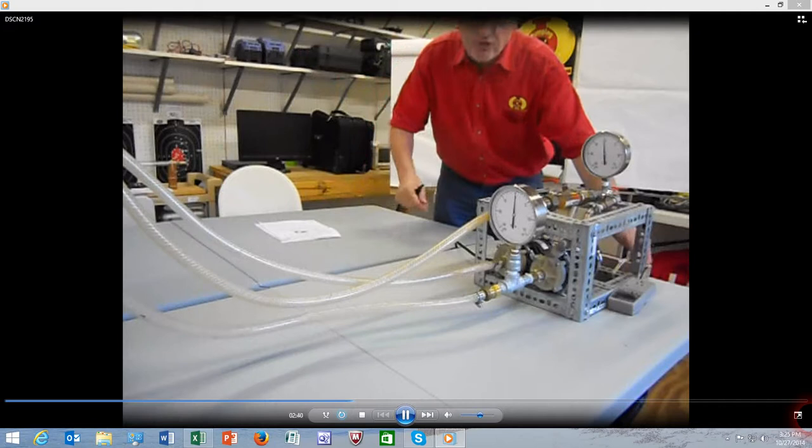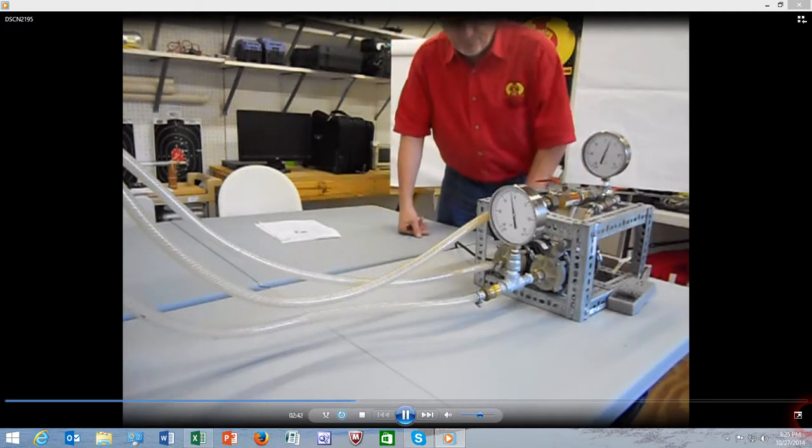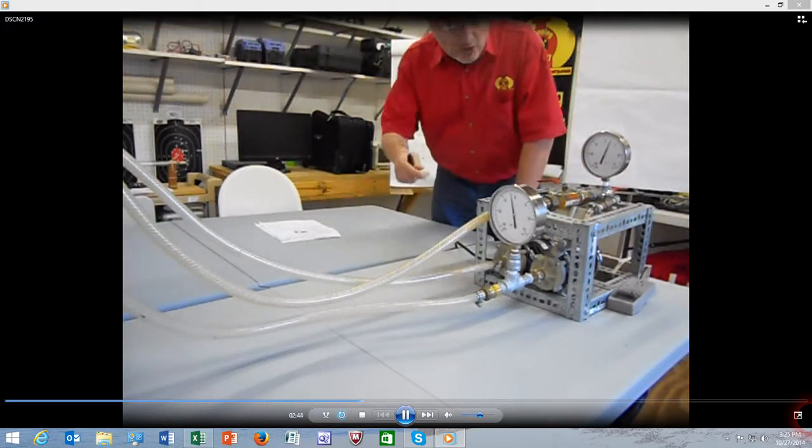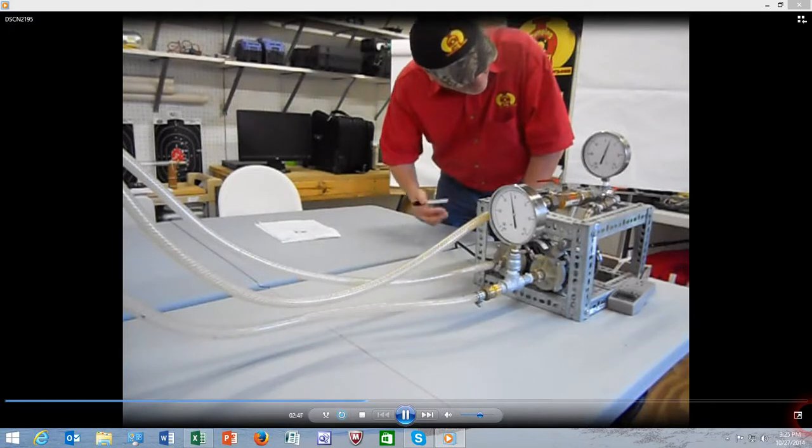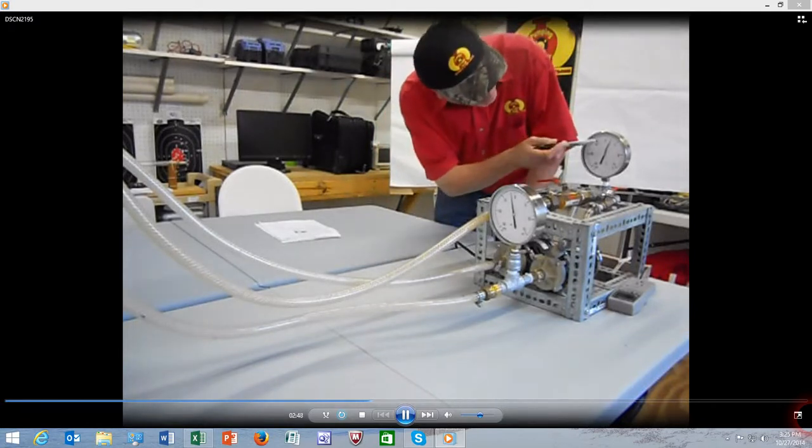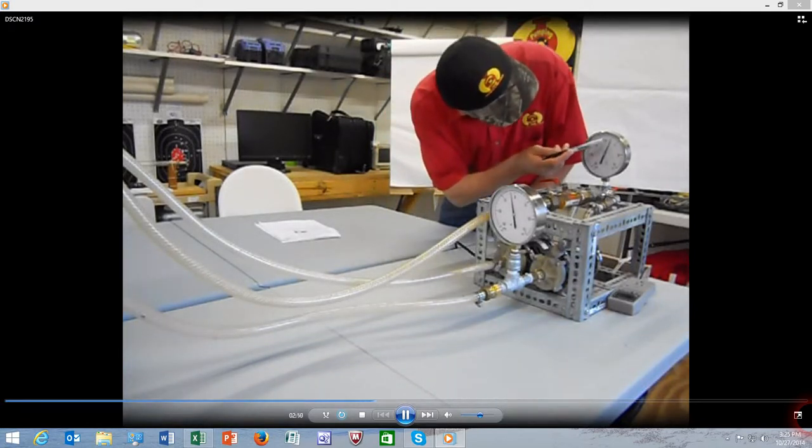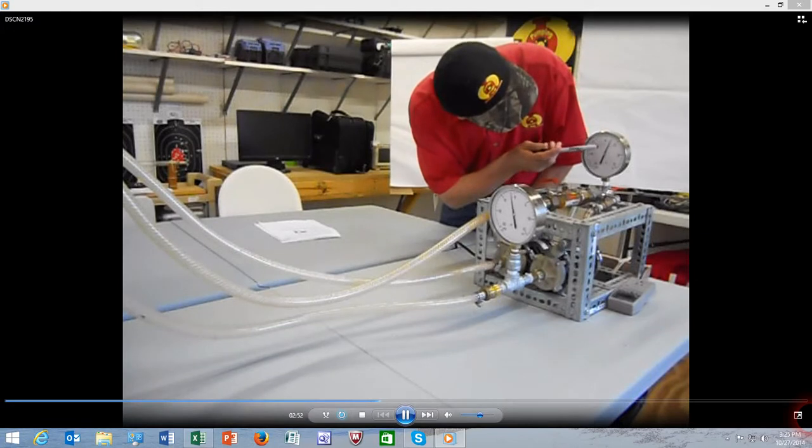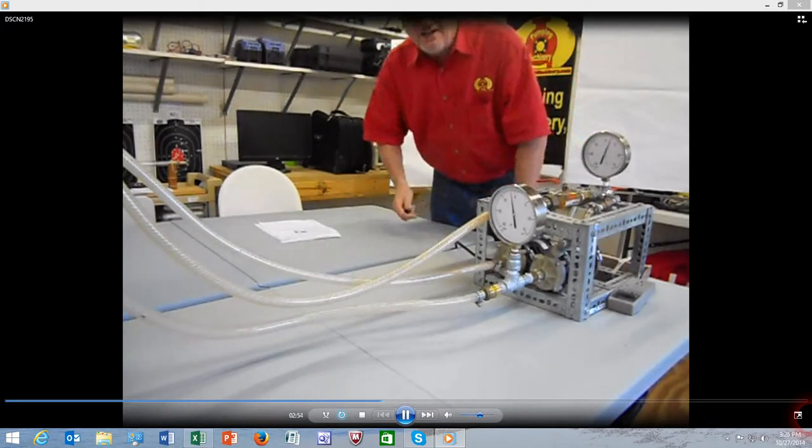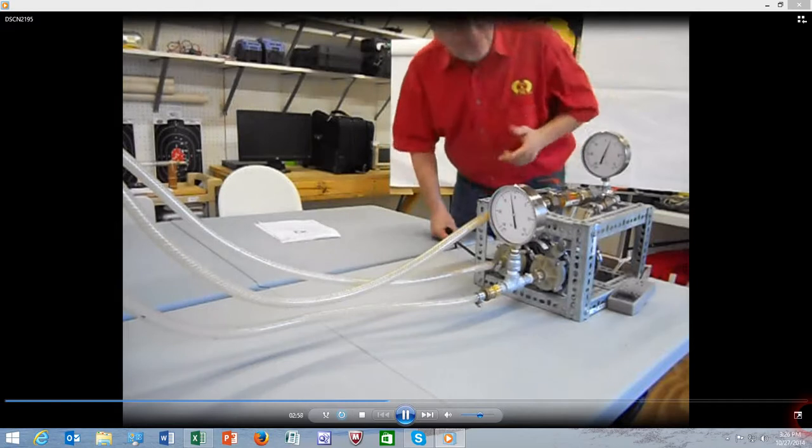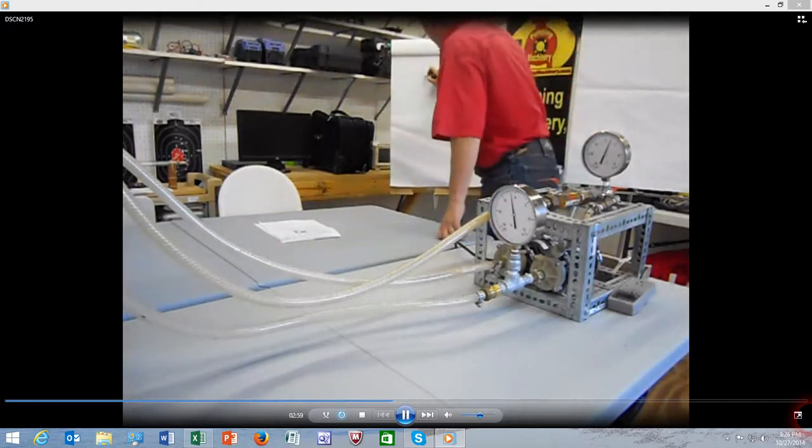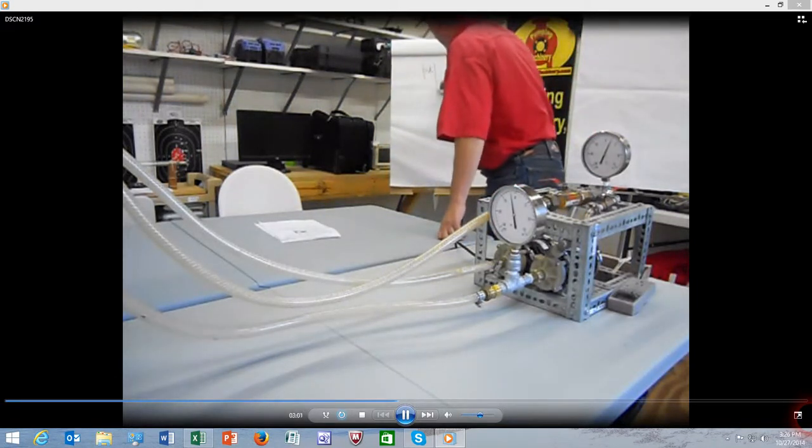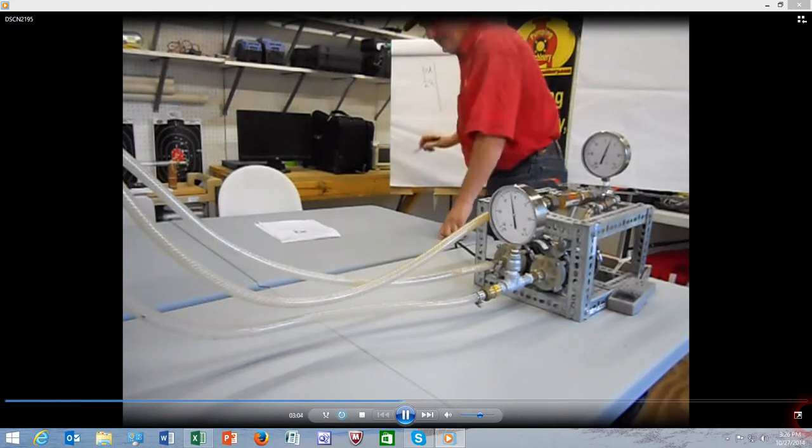So we're going to turn on pump number one. The valve is fully open for this particular test. And we can record the discharge pressure, which is perhaps 3 psi, approximately 2.8, perhaps. So we're going to write pressure P sub D, discharge pressure, is 2.8 psi.